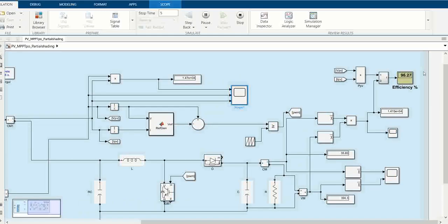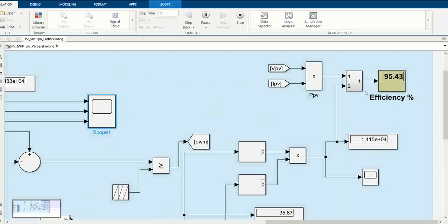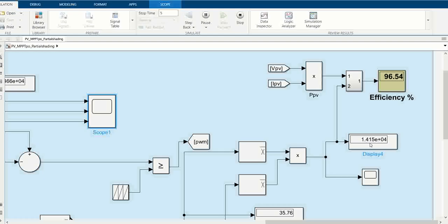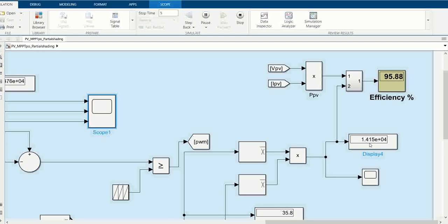You can observe that our system is very efficient - it gives us around 95 to 96 percent efficiency. You can see here that we get almost 14 plus kilowatt power. The power is a bit smaller compared to the PV power because there are some component losses included as well.